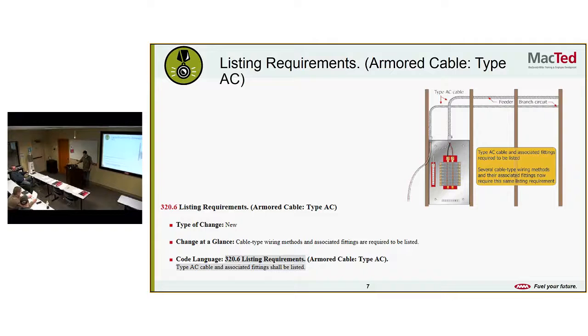Listing requirements, armored cable type AC. Looks like there's a new code here, listing requirements. Cable type wiring methods and associated fittings are required to be listed. So this is on the manufacturer end more than it is your end. So now they need to list fittings as being required for use. Looks like the code change was type AC cable and associated fittings shall be listed. So now they're saying they're listed.